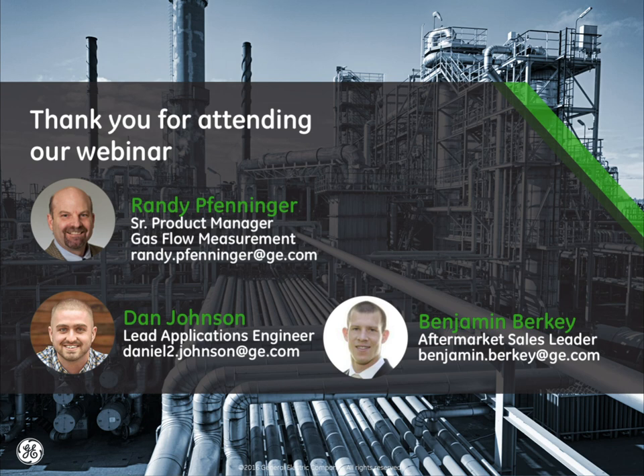So with that in mind, GE embarked on a CFD, or computational fluid dynamics, program. I think it's been going on like 3 years now, maybe even 4 years. Essentially what we've done is continue to catalog, understand and document the different changes in flow profiles and how they are affected by different changes in the upstream disturbances. With that in mind, we've been able to meet the accuracy requirements of these rules with as little as 8D, or 8 diameters, of straight run.